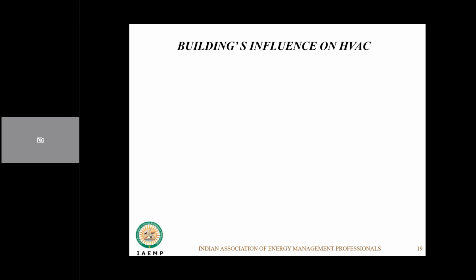Going further, let us understand what are the factors we need to consider from a building design perspective. So you have building orientation. In our scenario, tropical climate, if you have a building facing east-west, you will have a good amount of transmission gain from it. So you normally avoid building orientation east-west in our climate. You normally want to have a building facing north-south, so that your amount of heat gain from the transmission is limited. Sun path analysis, basically this is done from an understanding of, again, how the sun will affect the building heat gains.